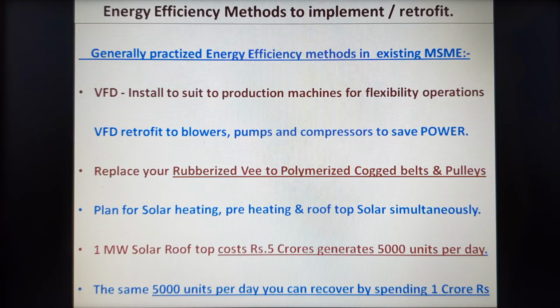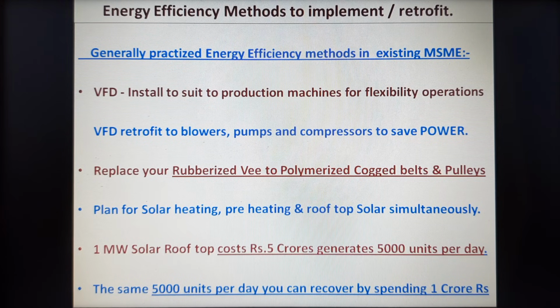So, let us see the methods to implement or retrofit in our MSME. I am just trying to discuss the generally practiced energy efficiency methods here. VFDs need to be installed in all our production machines for the flexibility of operations. This is not meant for power savings, but for the flexibility of operations. Whereas a VFD retrofit installed on blowers or pumps or compressors, especially centrifugal type, which are basically variable torque loads, definitely gives excellent or appreciable energy savings.